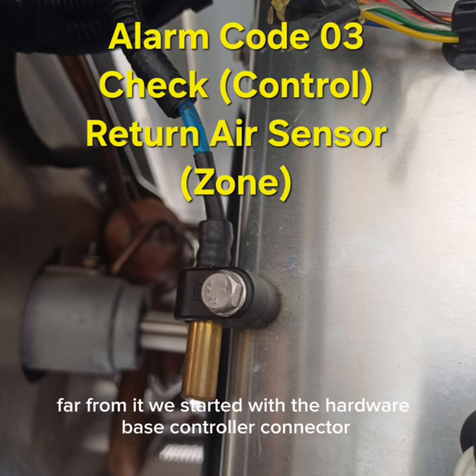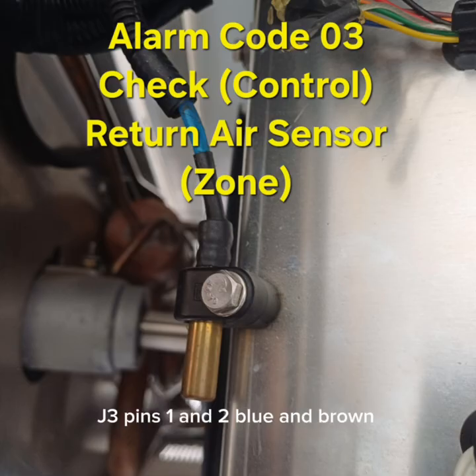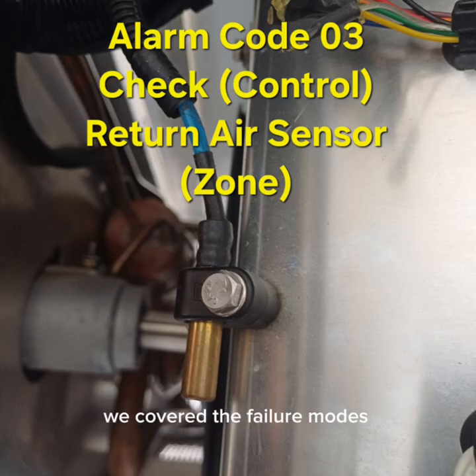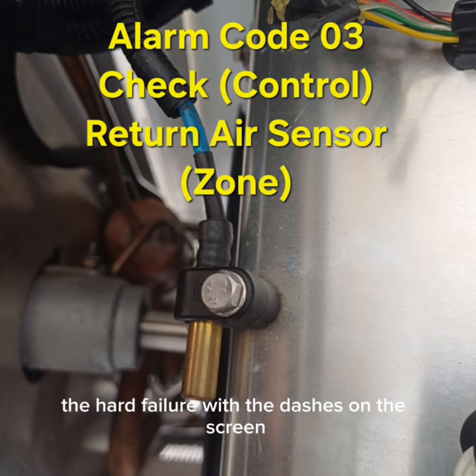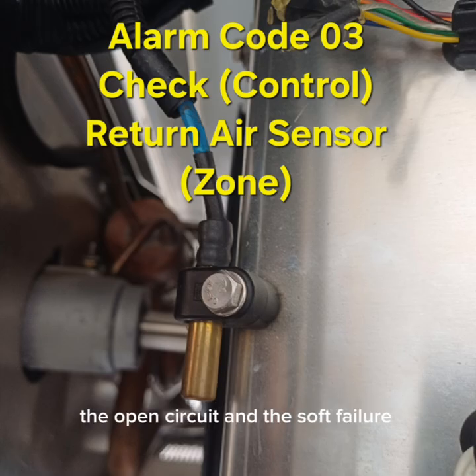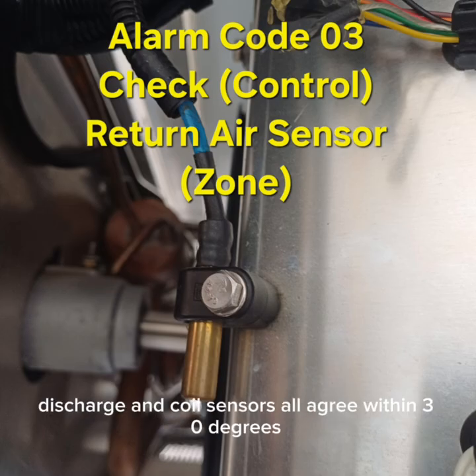Far from it. We started with the hardware: base controller, connector J3, pins 1 and 2, blue and brown. We talked about the installation physics. Barrel up, wires down. It's simple, but it stops the moisture that kills the sensor. We covered the failure modes: the hard failure with the dashes on the screen, the open circuit, and the soft failure, the drift. The believable lie. And we covered the big one, the logic test, the single degree rule. You cannot clear alarm 03 unless the return, discharge, and coil sensors all agree within 30 degrees.